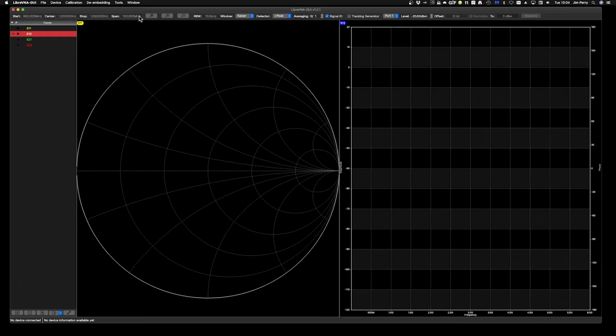That works just like the LibreVNA does. It works like a spectrum analyzer. I can give the device a start and a stop frequency, and it'll figure out automatically what the center of those 2 frequencies is and what the span is. All right. We can zoom in and out on our span by clicking the plus and minus magnifying glasses. Our resolution bandwidth, RBW, we can adjust on the fly.